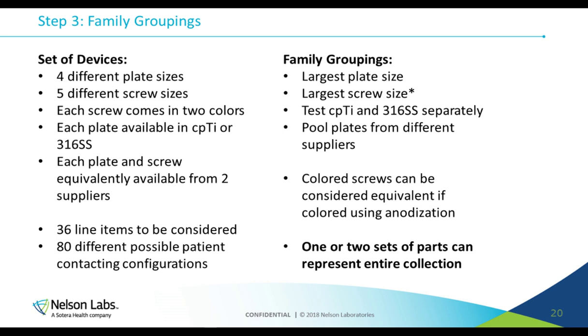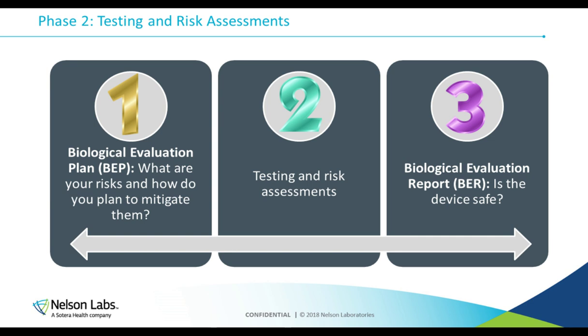That way, if somebody, like an auditor, goes into the warehouse and finds some screw at random and asks, how do you know that this screw is compliant with the MDRs? You say, well, let's take a look in our biological evaluation report. We say, okay, this part number is included in this report. It's not the exact screw that was tested, but it was proven to be equivalent to that other screw if that was tested. And that way everything is tied together, nice and neat, and the entire product catalog as it sits on the warehouse shelf is covered.